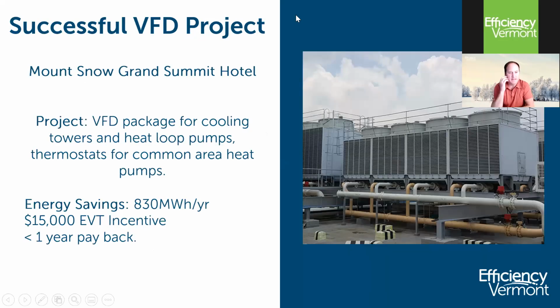So here's a little example. Cooling towers are just a home run. If it's not a modern cooling tower, and I mean one put in the last 5 years that's been subject to energy code and probably has VFDs on every pump and fan, you'll run into a lot of cooling towers that don't have drives on any of the pumps and fans.